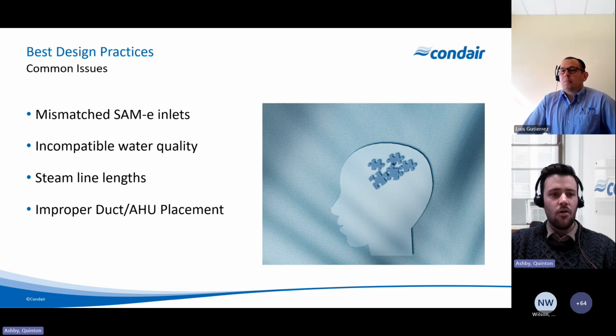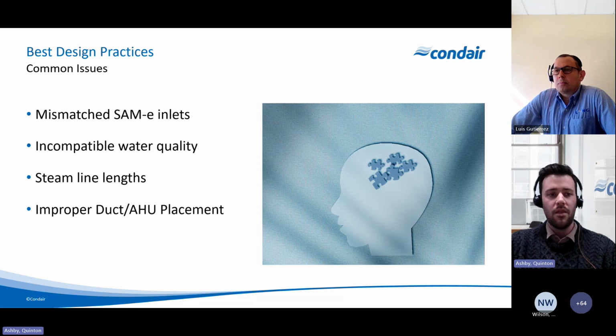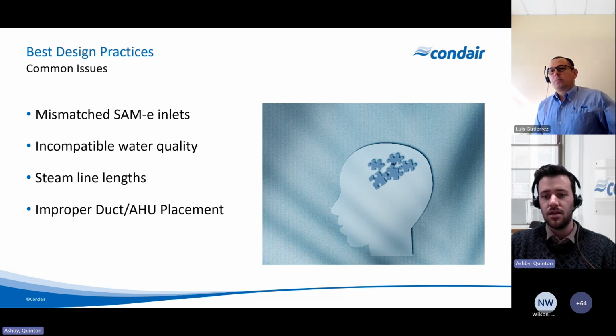Kind of at the end of this now, some common issues that we see in the field that we want to get across. One of them is mismatched sizes. So this is our SAM-e, a distribution manifold, and this holds true for all manifolds. Anytime there's a mismatched inlet, say you have a 3-inch line and you're reducing it to a 1/2-inch inlet, that's going to increase a lot of back pressure to the unit itself, and it's not really viable. So if we're pairing a humidifier to a distributor in an air handling unit, we want to make sure that they're the same size and that they are paired together properly.